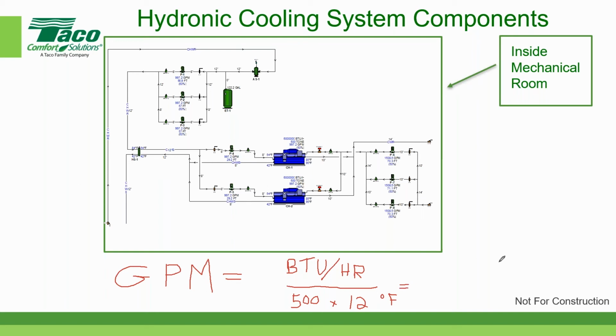Anybody want to guess at that one? How many BTUs per hour is equal to one ton of cooling? Well, while they're trying to figure that out, I'll just write it out. I see a lot of 12,000s popping up. So you take 12,000 and you divide that by 500, and you divide that by 12. Simple arithmetic: 12 goes into 12,000 a thousand times, and 1,000 divided by 500 is equal to 2. So that's 2 gallons per minute per ton.